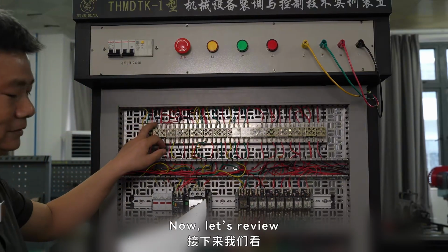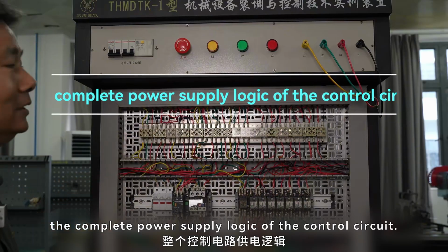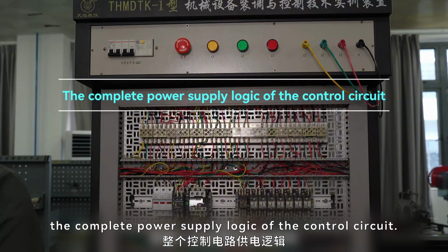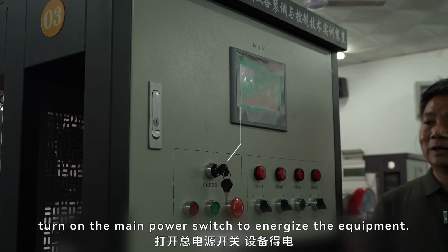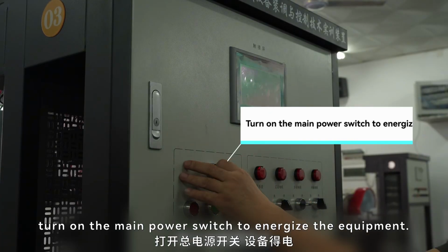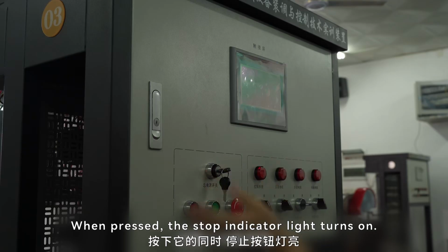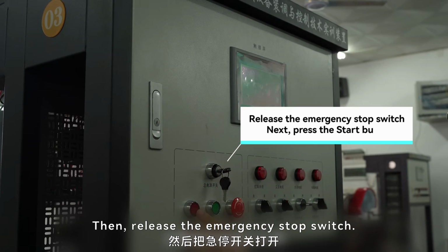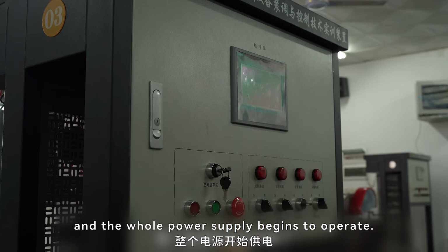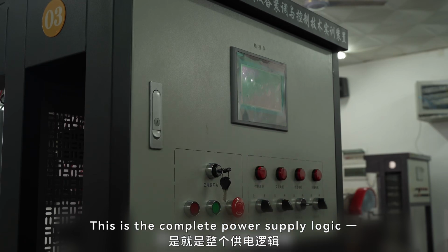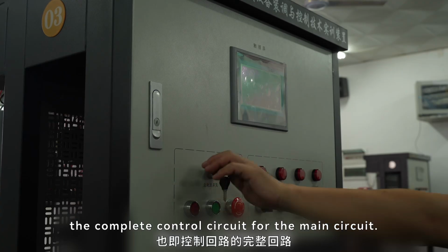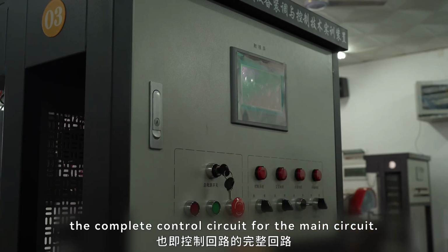wire. Now, let's review the complete power supply logic of the control circuit. First, turn on the main power switch to energize the equipment. When pressed, the stop indicator light turns on. Then, release the emergency stop switch. Next, press the start button, and the whole power supply begins to operate. This is the complete power supply logic, the complete control circuit for the main circuit.